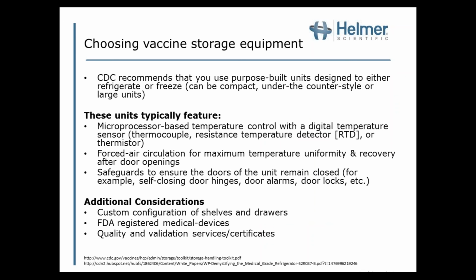As I mentioned, the CDC recommends you use purpose-built, pharmaceutical-grade units designed to either refrigerate or freeze. The reason you don't want combination units is that the cold air from the freezer in a typical combination unit will actually blow into the refrigerator, causing a lot of fluctuation.